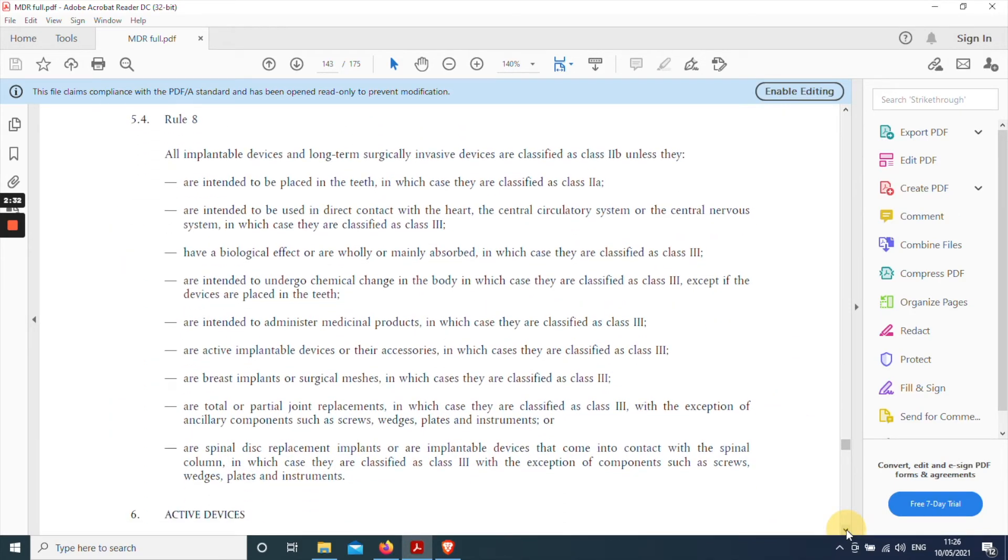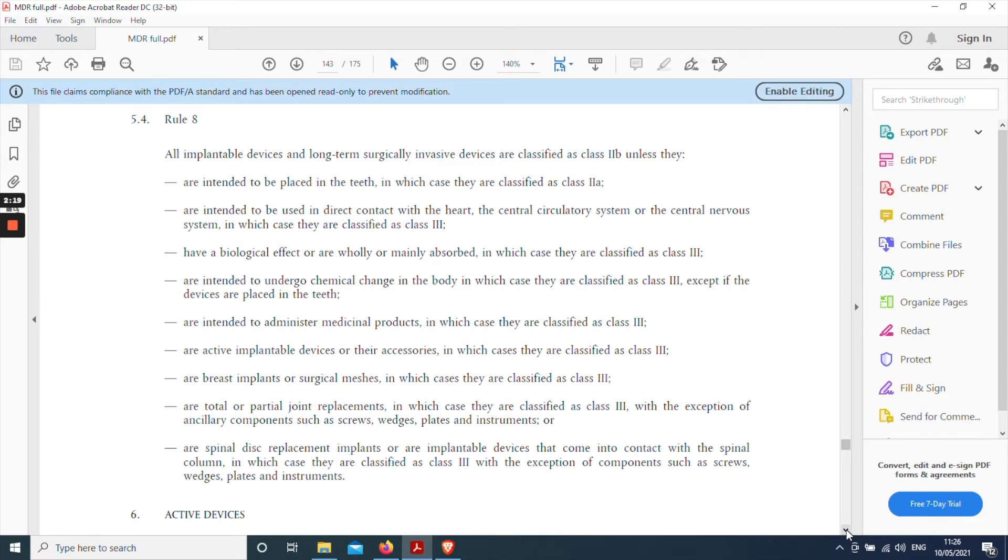And move on to rule eight. All implantable devices and long-term surgically invasive devices are classified as class 2b unless. So we're in the correct section here. Implantable and long-term surgically invasive devices. That's what a pacemaker is. So the default position is that it's class 2b unless one of the exceptions in the following list applies. This list is referred to as indents. And we need to look at each indent in turn to see if we have an exception.